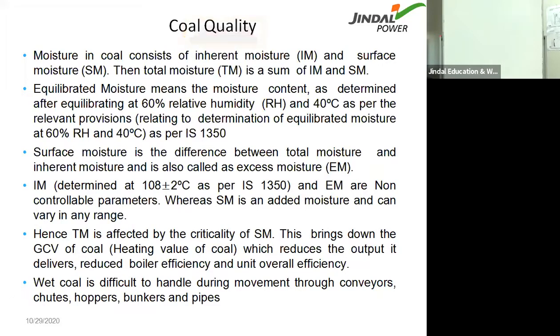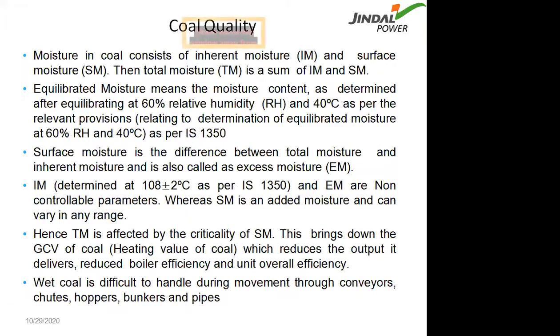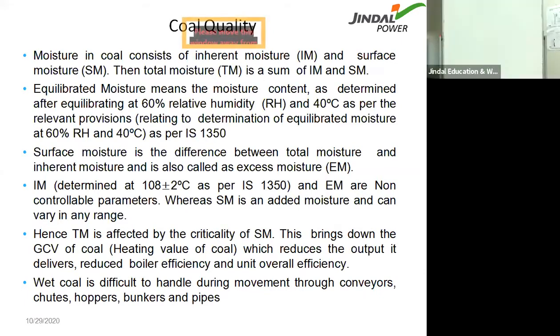Inherent moisture is the molecular moisture present in coal. It can neither be extracted nor evaluated by any simple process. To determine this inherent moisture, you have to heat the coal at 108 plus minus 2 degrees centigrade as per the IS 1350 process.